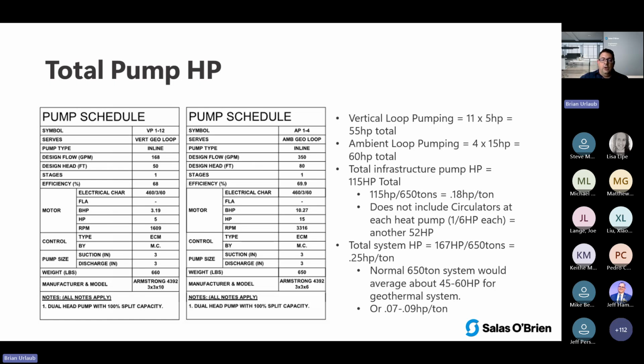So you've got ground loop pumps, you've got ambient loop pumps, you've got building connection pumps, and then you've got pumps within the building. Now, of course, your building-by-building pump energy is less than if they had their own geo, because they're just connected with 2 pipes to the ambient loop, very low pump energy. But the infrastructure pump energy is something to be considering. And you always want to look at this. And that's, again, back to the single pipe. If it's done right, and you model that correctly, and you look at your delta T's from energy source to energy source, and you put in more than one energy source, so you can bring that total flow rate down, it does make a big difference.